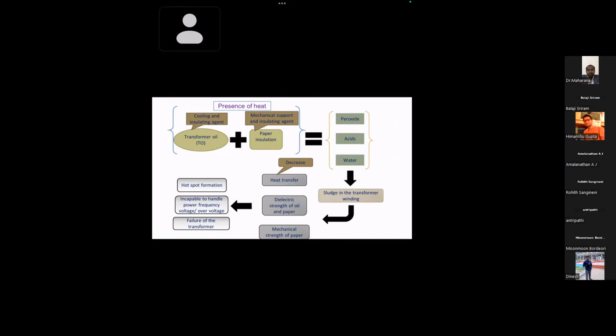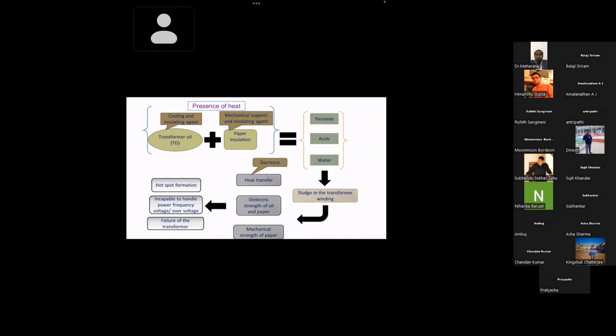Generally, when combined with heat, it leads to the generation of peroxide, acid, and water, and these three combinations are deadly. They produce sludge, which may contain some ferrous particles. There may be some carbonized content. When these particles circulate in the oil in a functioning transformer, that will lead to hot spots, uneven temperature distribution, and temperature gradients.